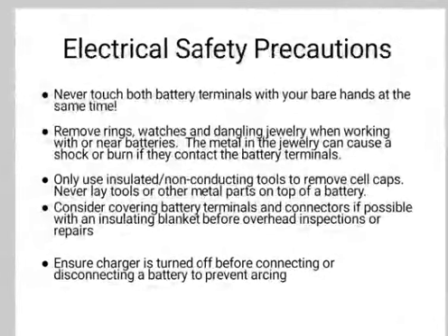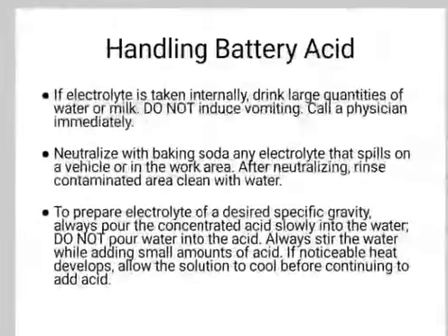Always wear proper eye, face, and hand protection. Use a non-metallic container to handle the concentrated liquids. Use extreme caution while handling electrolyte and keep an acid neutralizing solution readily available as a precautionary measure. If electrolyte is consumed internally, drink large quantities of water or milk. Do not induce vomiting.